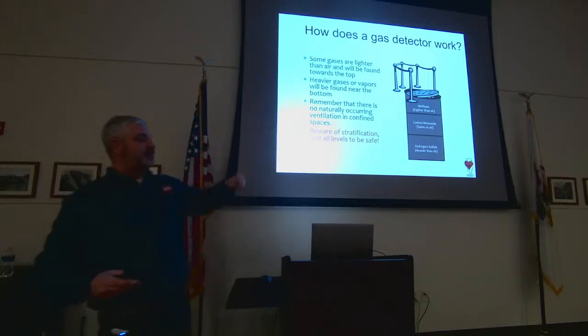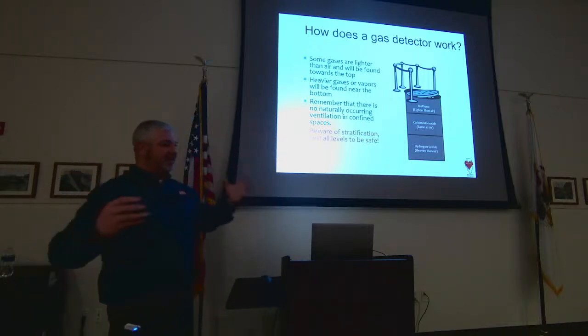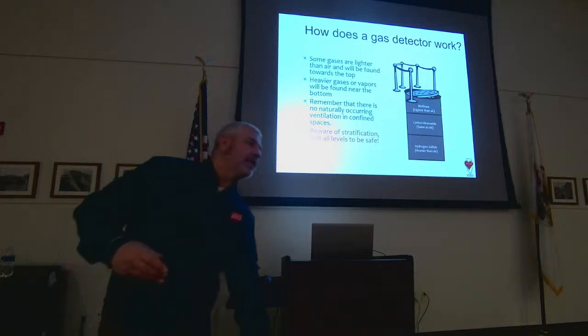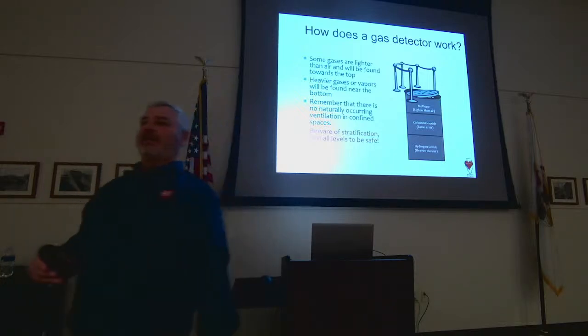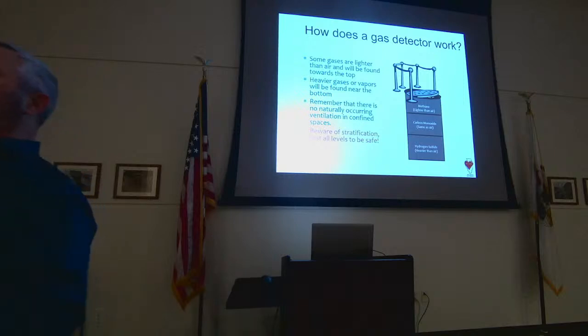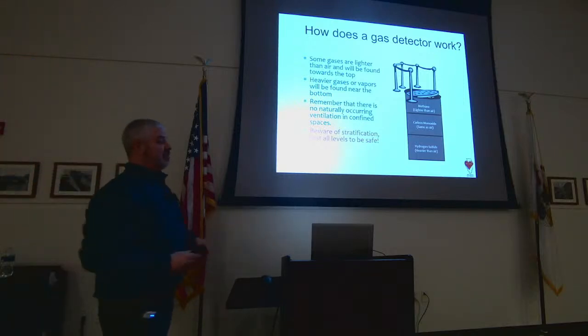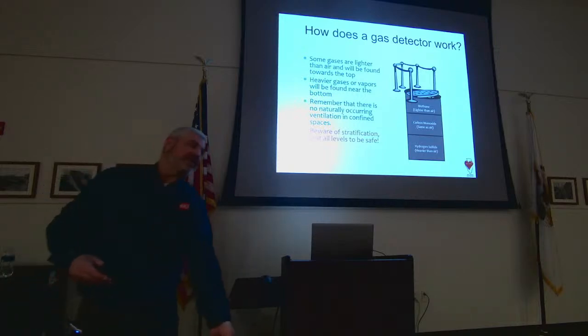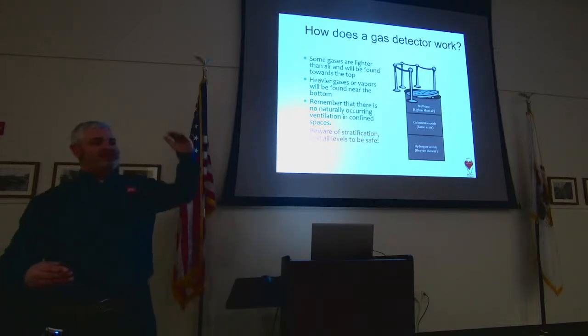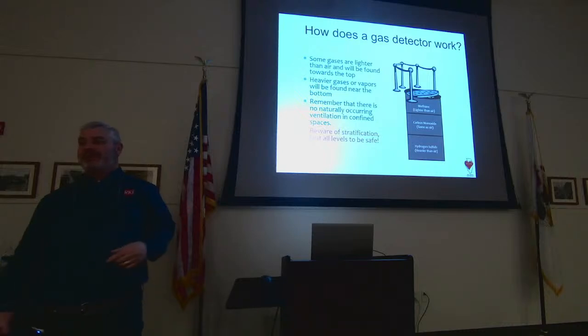That way you can capture the methane, you can capture the carbon monoxide floating around in the air, and you can drop it down low to measure that hydrogen sulfide or those heavy hydrocarbons. You want to make sure you measure the whole atmosphere prior to entering into it. So it's not just pull a sample and say I'm good to go, you've got to incrementally measure depending on the depth of it.